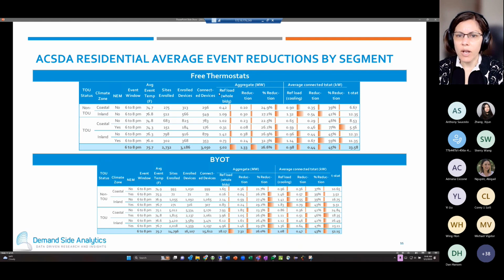We also summarize things not only as a percentage of the whole building load, but also as a percentage of estimated cooling load. We do an analysis identifying the weather-sensitive component of the load using historical loads versus the component that is not weather sensitive, and if you subtract that part out, that is the inferred cooling load.